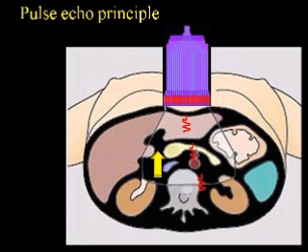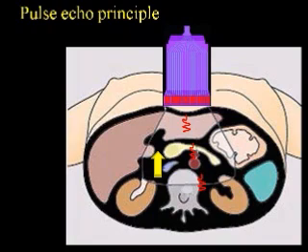The pulse echo principle works as follows: from the piezoelectric crystals in our probe, ultrasound beams are propagated in a pulse wave fashion at small intervals. When these beams get reflected back from tissue in our body, by measuring the time between sending the ultrasound and receiving the reflected signal, the machine determines the distance at which that reflector is situated. This is how different tissues are assigned different depths in the image.